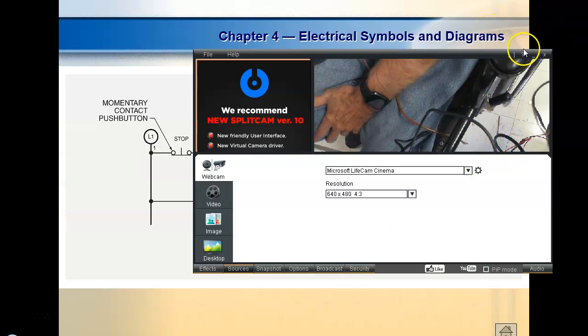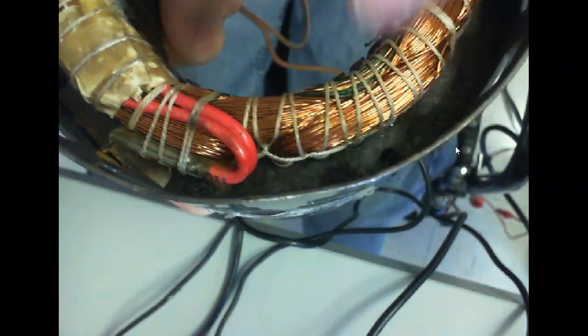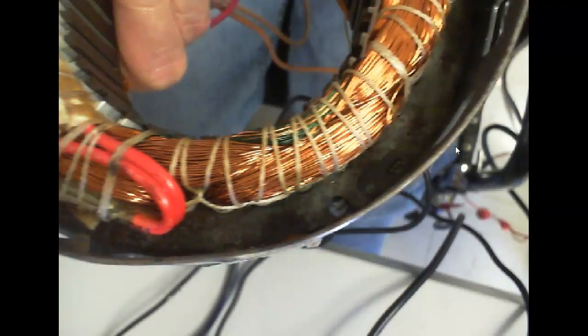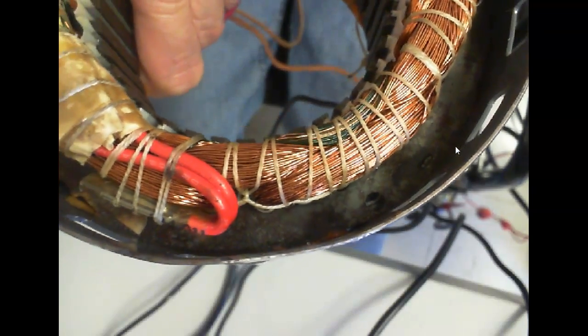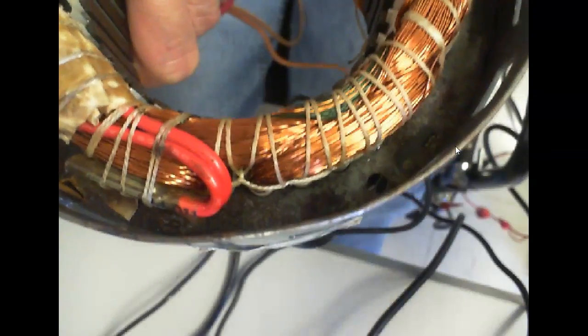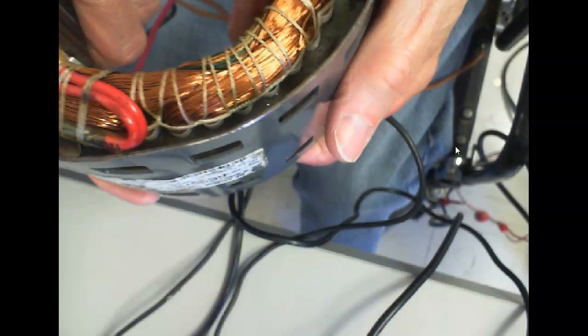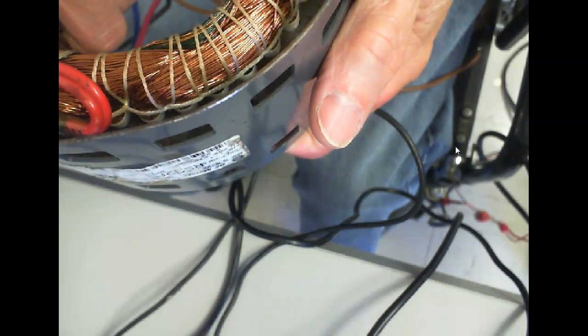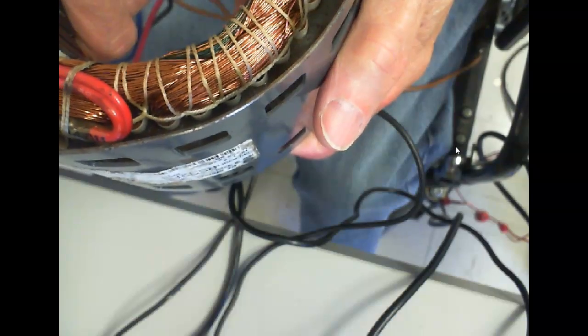So this is a stator. This is a multi-speed single-phase motor, so that's why it's got all the leads in it. And there's the overload right there. It's a thermal overload, so it's built into it. These guys will get you hurt because they'll trip if it overloads the motor, and when they cool down, what will they do? They'll reset. They reset themselves. So if you're on a blower motor and the motor's not running and you don't pull the disconnect, it might be because it's got an overload, right? And then when it kicks back in, if you got your hands inside there, you're going to be hurt.